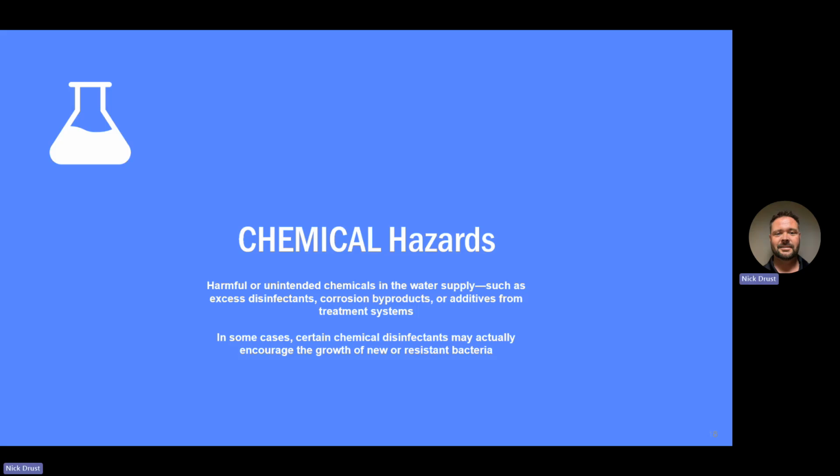Poor water chemistry can contribute to scale buildup, corrosion, spotting, instrument damage, shortened equipment life, and inconsistent reprocessing outcomes. Chemical hazards can also influence microbial risk. For example, inadequate disinfectant residuals may reduce the ability to control bacterial growth, while corrosion and scale can create surfaces that support biofilm formation.